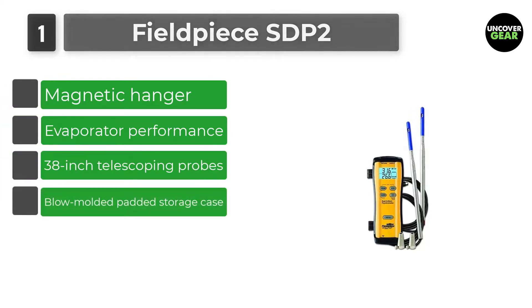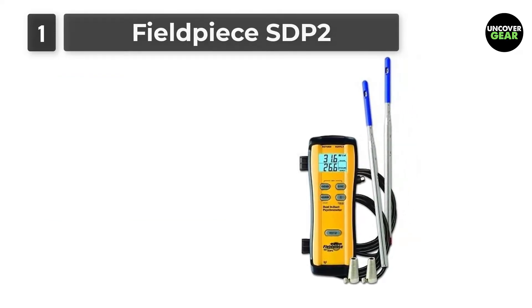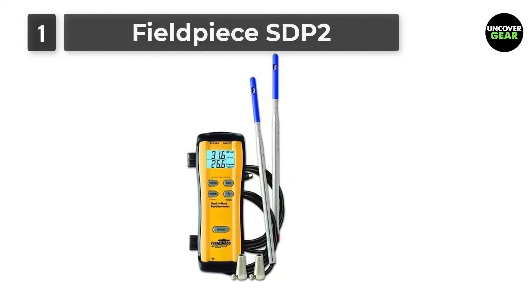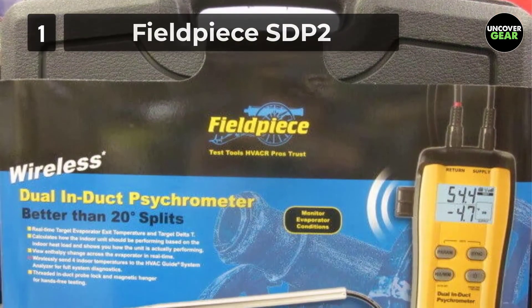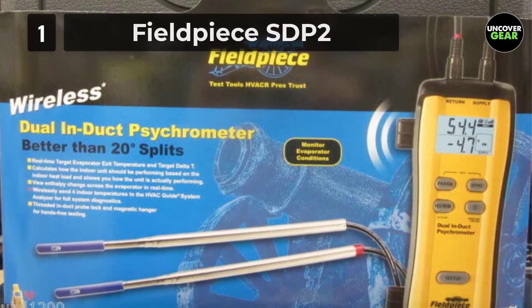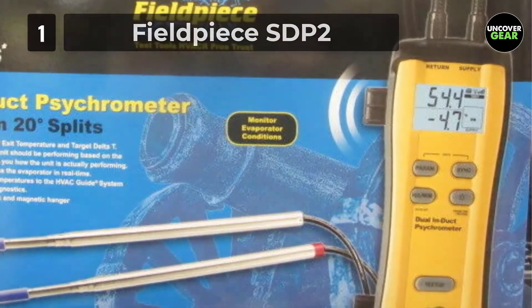The SDP-2 Dual In-Duct Psychrometer is more than just your everyday HVACR psychrometer. It gives HVACR professionals more insight into HVAC evaporator performance than any other psychrometer, because it takes 4 evaporator measurements at one time: supply wet bulb, supply dry bulb, return wet bulb, and return dry bulb. So HVACR professionals get a live, real-time snapshot of the evaporator performance, even while conditions are changing.